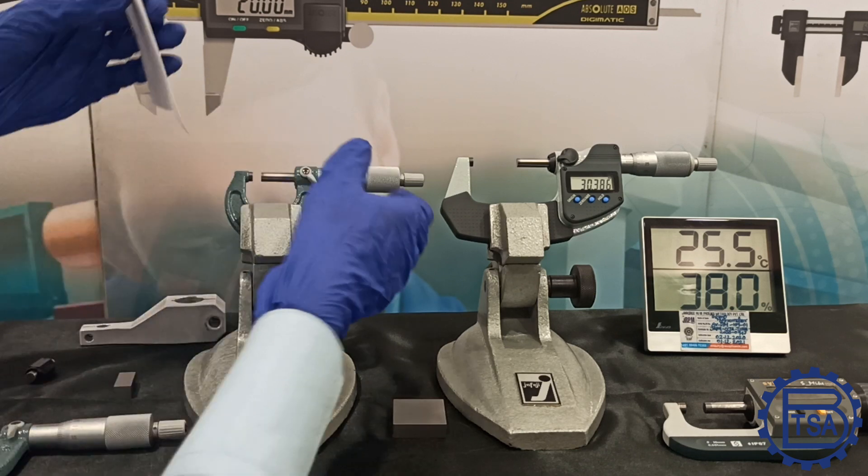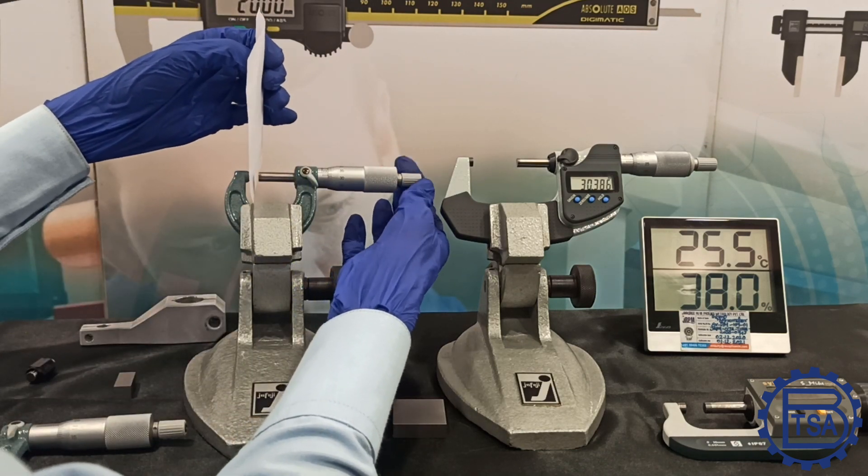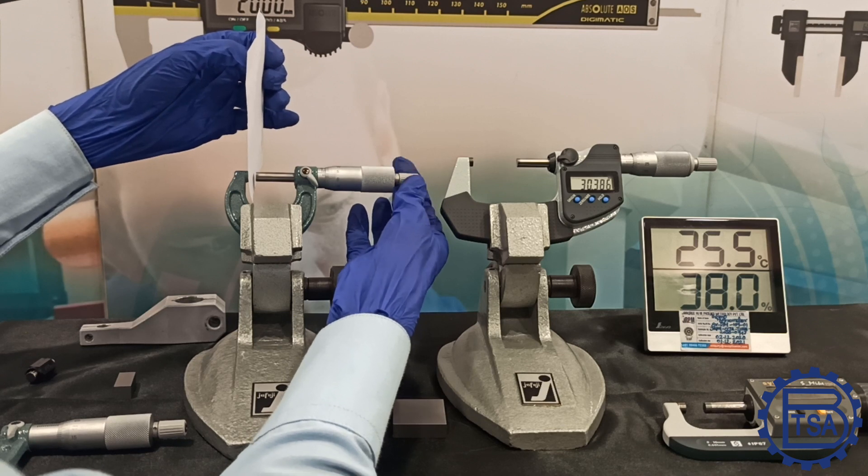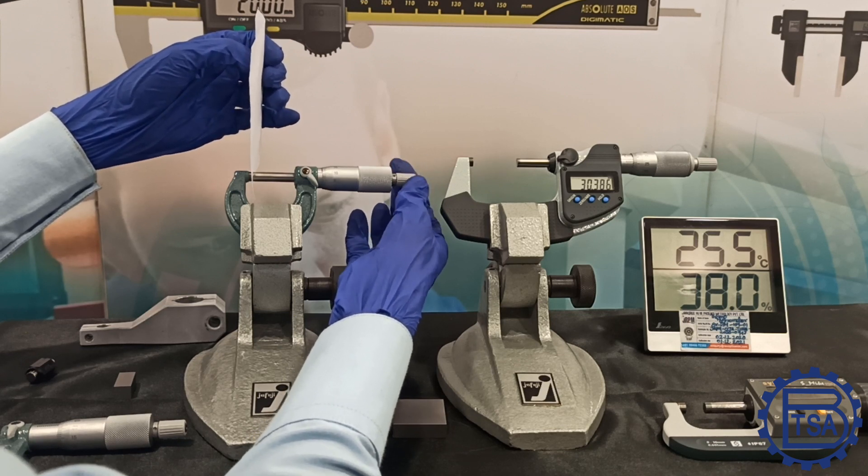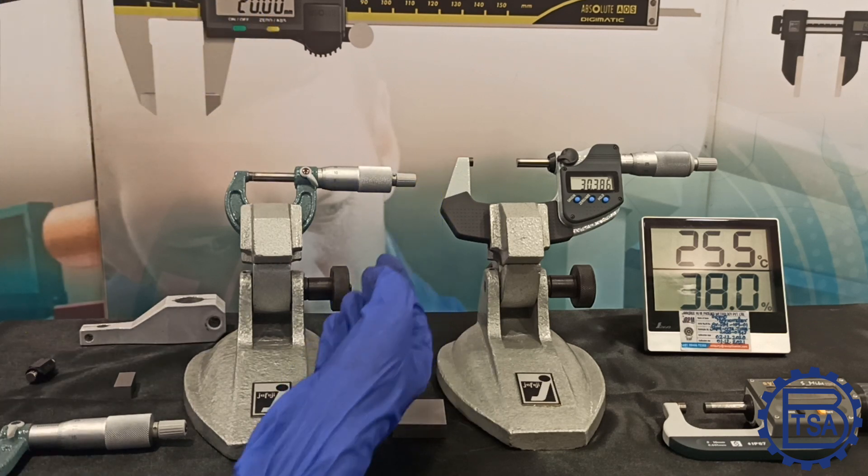Use a paper and make the measuring faces to be in contact with each other and gently pull the paper out. This can completely clean the measuring faces.